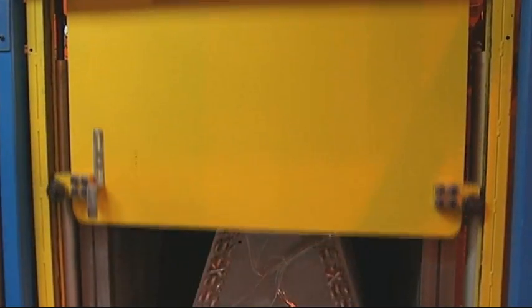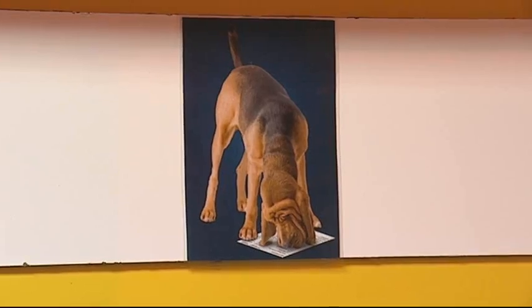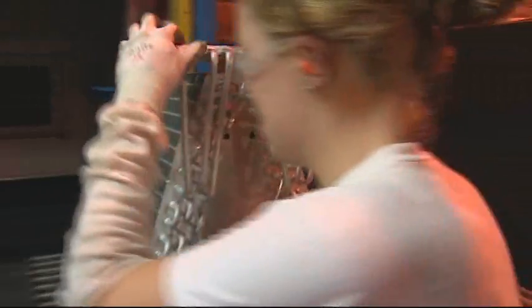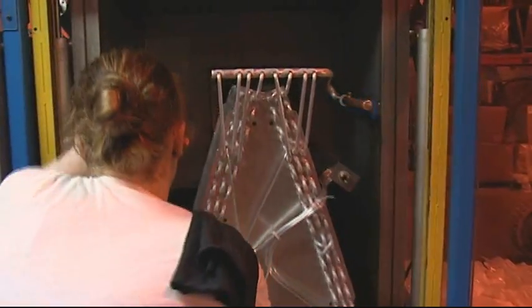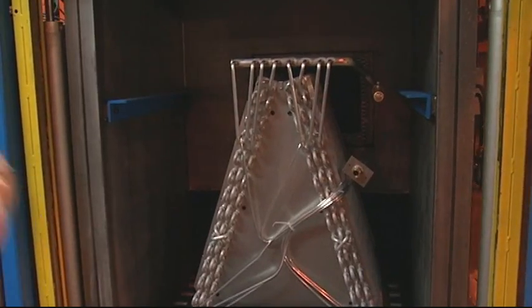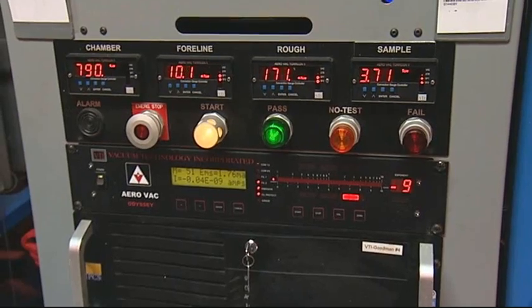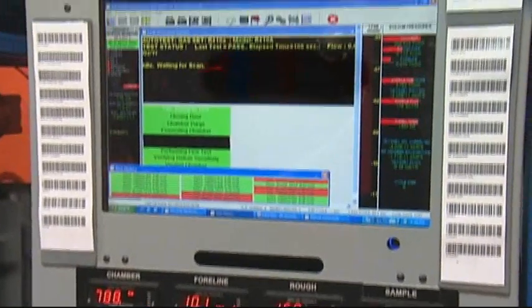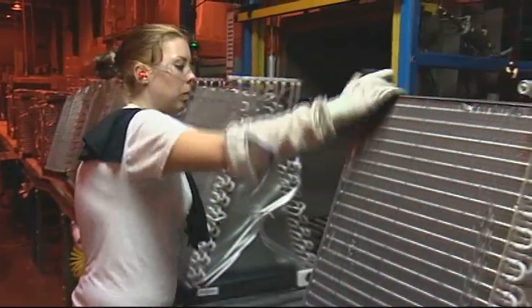Here we are at the hound dog. We're checking every joint at one time for a potential leak. If it has a leak rate higher than half an ounce a year — 0.5 ounce a year — then it retakes. Half an ounce a year? That is very, very impressive — that's an extremely small tolerance.